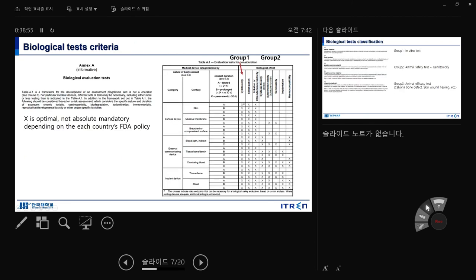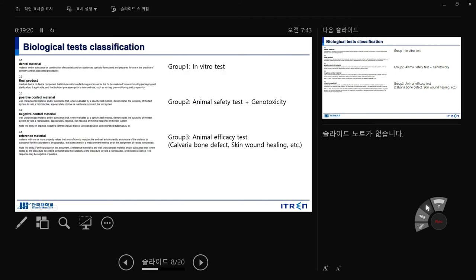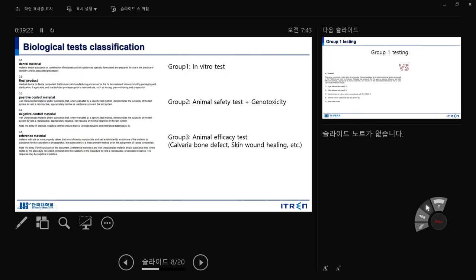Question from student: does a blank in the Annex A table mean it's unnecessary or can be ignored? Answer: a blank means you can absolutely ignore it. An 'X' is optional but not mandatory — it is highly recommended to do everything, but depending on your situation you can adjust. We have three groups: Group 1 is in vitro study. In the ISO standard they mention cytotoxicity basically, because this standard is about biocompatibility, not functionality.